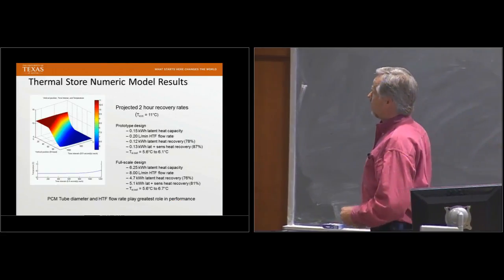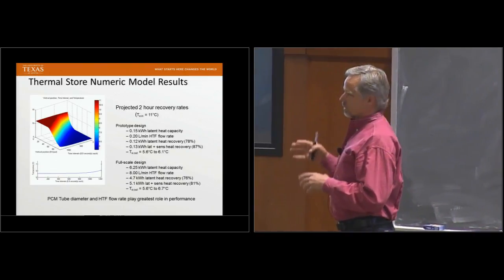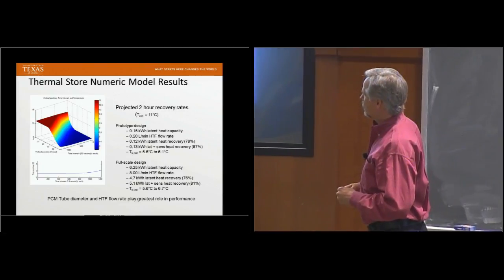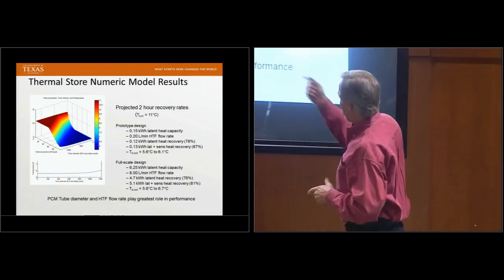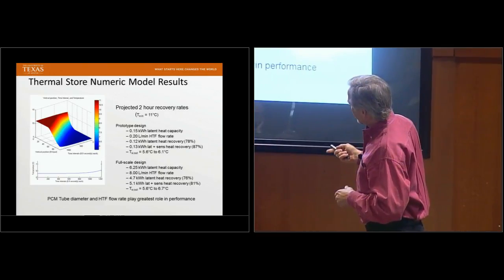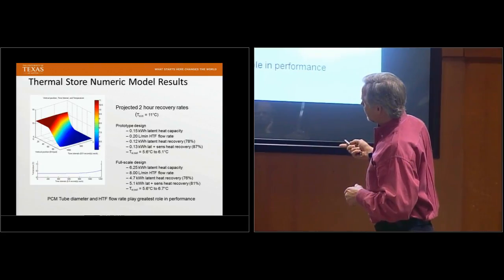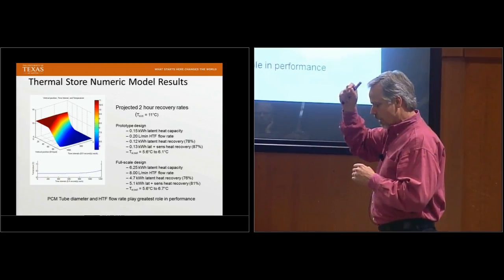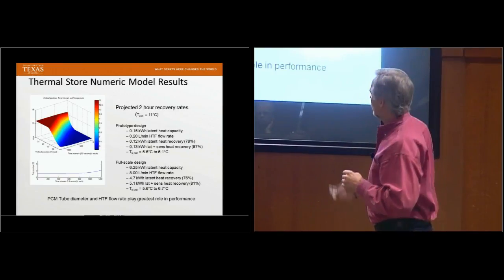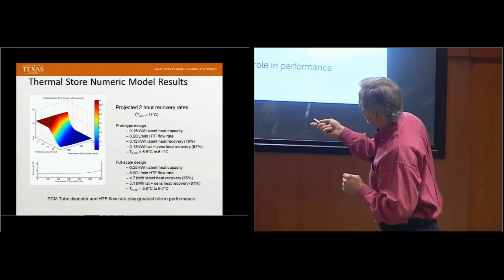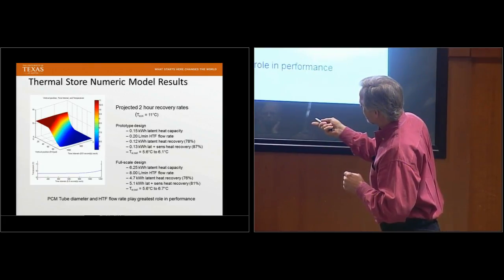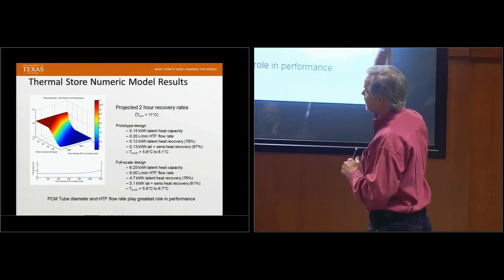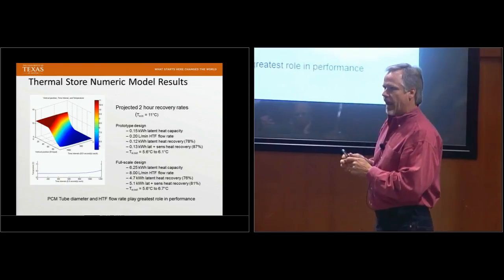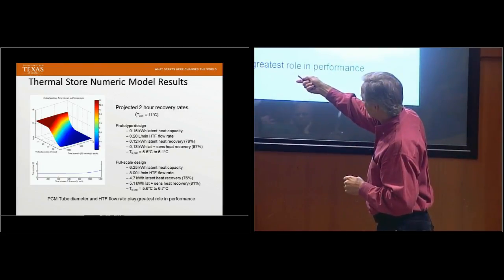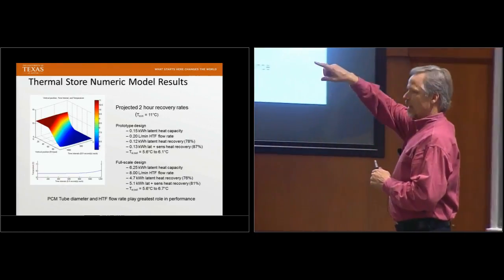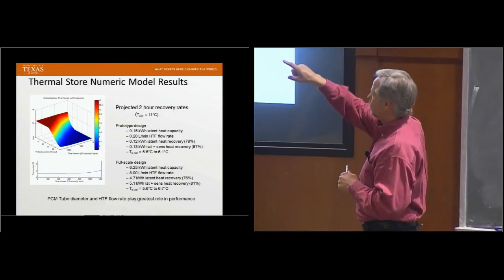Now, these are the results of the numeric model run for both the small-scale prototype and the full-scale prototype for the facade thermal lab. Let me explain what you're looking at here, because I see it easily, but you might not. This axis is time. As time goes by, I'm recording the water temperature from top to bottom in the thermal store. This is the location from the top, so 0 is the top, and all the way at the end is the bottom. And this is the temperature in the store. If you took a slice this way of this graph, you would have, at that specific moment in time, a plot of the water temperature, the heat transfer fluid temperature, from top to bottom in the tank.